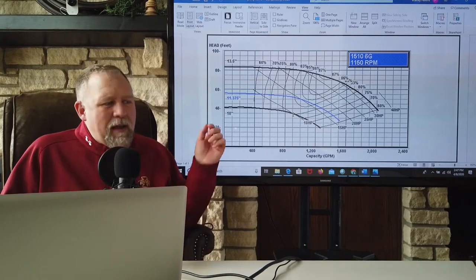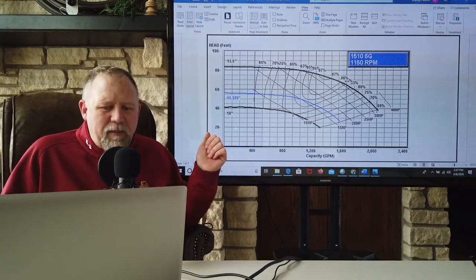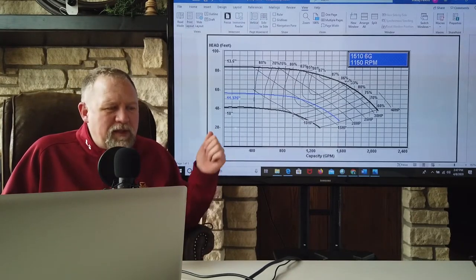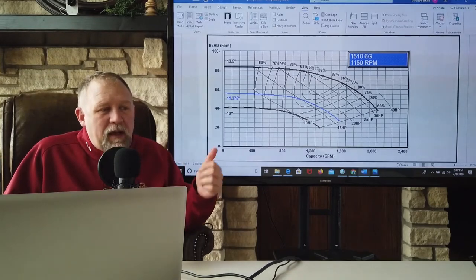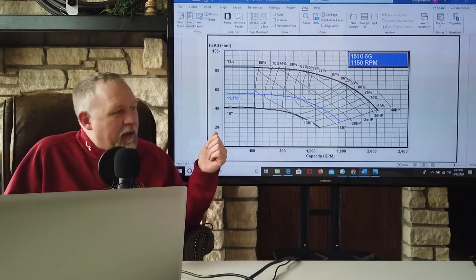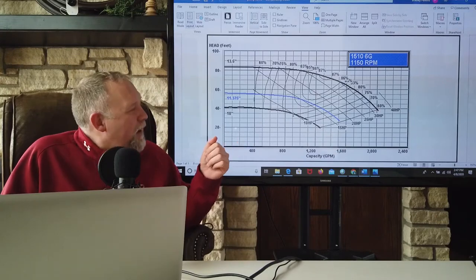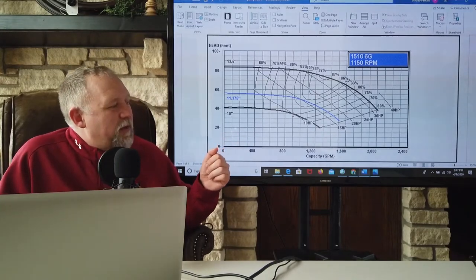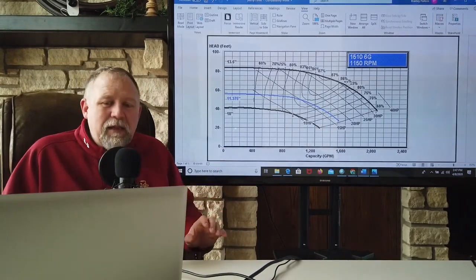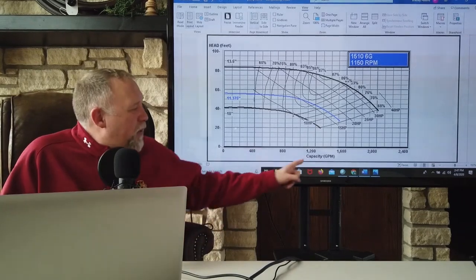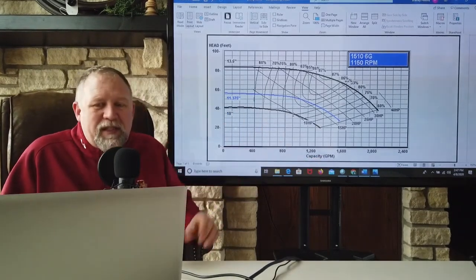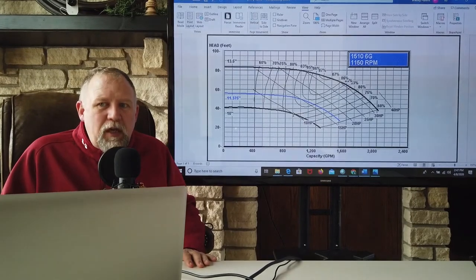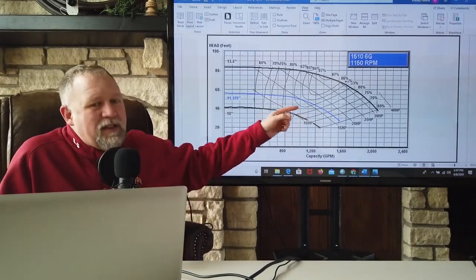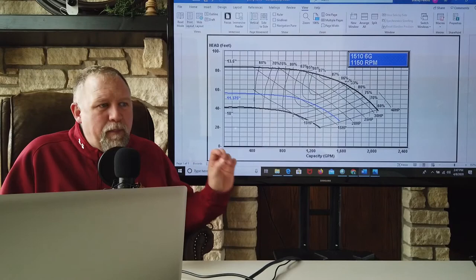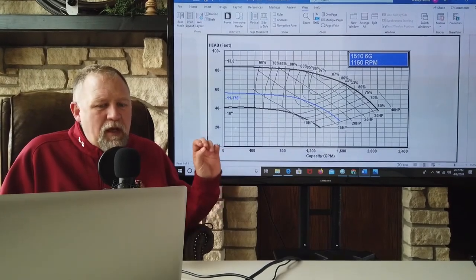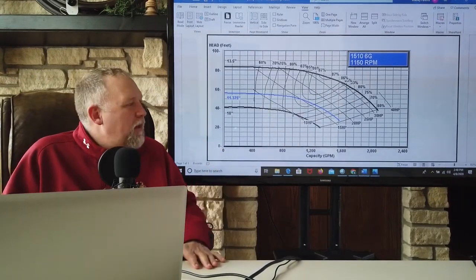So think back to that boiler system and pumps, the flow diagrams that we looked at for the last lecture. And for me, that was just earlier today. But maybe you watched that lecture a few days ago. Well, if that's the case, you might know the gallons per minute that you need to put through a system, but really, you don't know the exact pressure loss until you add up the resistance for every pipe, elbow, and fitting, and twist and turn in the system.